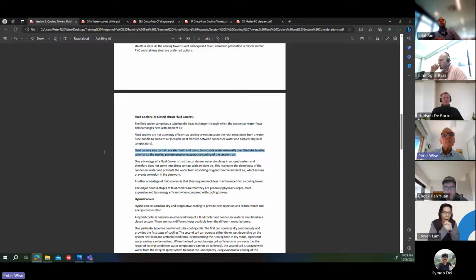A fluid cooler also contains a water basin and a pump to circulate water externally over the tube bundle to enhance the cooling performance by evaporative cooling of the ambient air. I'll show you a picture of, well, that diagram shows it anyway. You can see a pump down the bottom. It brings up some of the water, which dribbles down over here, over the tube bundle, and enhances the performance. But essentially, it's a dry cooler.